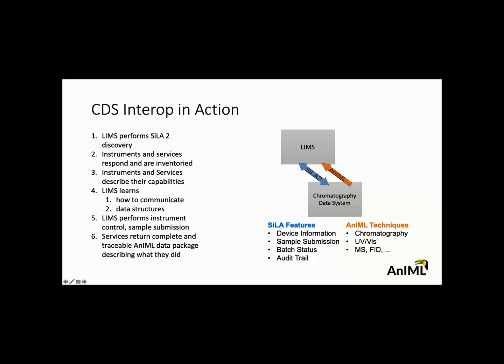And when you combine SiLA and AnIML here, the LIMS can discover, on the one hand, what the SiLA features are. So how can I send commands, and how can I check the status on my batches on the chromatography data system. But at the same time, I can discover what the data will look like that the CDS returns once it's done with the run. And that way I can build sophisticated integrations without custom code, which is a novelty. And then I'm in a position to control my instrumentation, submit samples, get status updates, and the service will then return a complete and traceable AnIML data package describing what that did.